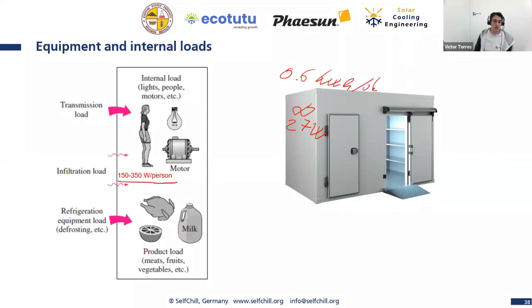Then we have persons inside the cold room. We don't usually have one person staying inside, just putting products there for a couple of minutes. But if you want to consider it, a person, depending on condition, produces 150 to 350 watts. So if you're 1 hour inside the cold room, that's 150 watt hours, more or less, just to give you a feeling.